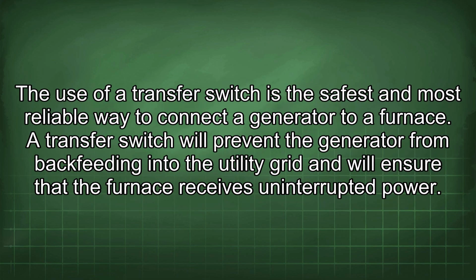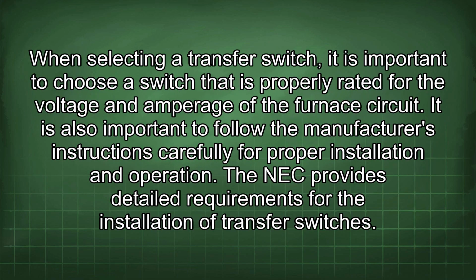The use of a transfer switch is the safest and most reliable way to connect a generator to a furnace. A transfer switch will prevent the generator from backfeeding into the utility grid and will ensure that the furnace receives uninterrupted power. When selecting a transfer switch, it is important to choose a switch that is properly rated for the voltage and amperage of the furnace circuit. It is also important to follow the manufacturer's instructions carefully for proper installation and operation.